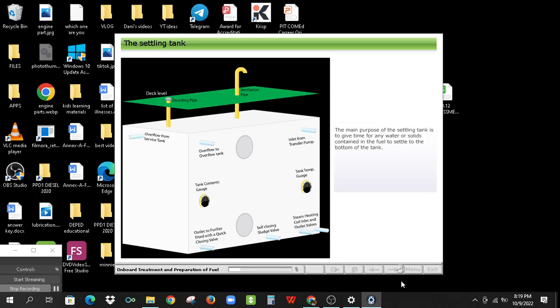The main purpose of the settling tank is to give time for any water or solids contained in the fuel to settle to the bottom of the tank. The tank is provided with a drain cock, which should be operated regularly to remove as much of the settled water and dirt as possible. This settling or separation occurs due to the fact that the water and dirt have a higher density than the fuel oil, and over time, gravitational forces will cause these heavier components to pass to the bottom of the tank.